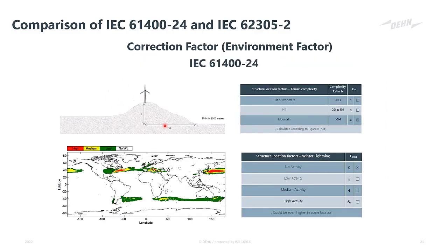Now, the correction factor for terrain complexity is calculated based on this graph or this image in IEC 61400-24, where we look at the peak value of the hilltop on where the turbine is based, if any, and then the distance away to the first or the lowest terrain. From that, we use H divided by D, and we get a ratio, and then we select the factor. Winter lightning is also given in IEC 61400-24, so you can see, again, a global view, and you select in your country based on this scale what the lightning activity in winter would be in your region, and you select that.